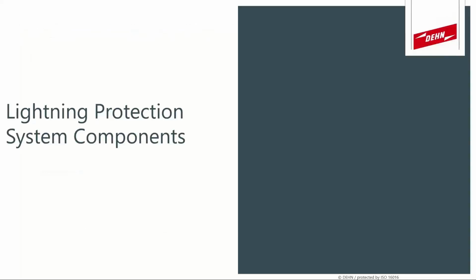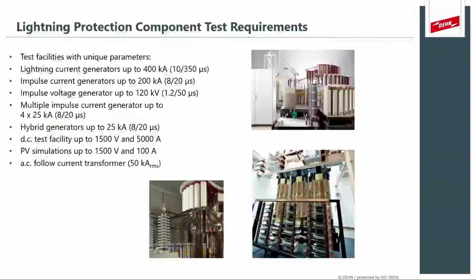Now, to further investigate the lightning protection capabilities or the performance of such a grounding system, we need to also understand that components are tested differently for lightning frequency and lightning currents, because these are very high currents with very high mechanical strain. And there's a lot of different parts that we do test. We test anything from clamps to spark gaps to isolated lightning protection systems. And what's quite interesting is at DEHN, you can actually see this is our lightning generators. So at DEHN, we have a facility in Germany where we can test up to 400 kA 10/350 or direct lightning currents. And we can test all the components and surge arresters and do a lot of research and development. To the best of my knowledge, last I heard, this is the biggest lightning current generator in the world, actually. So there's a lot you can do with this around testing such high currents.